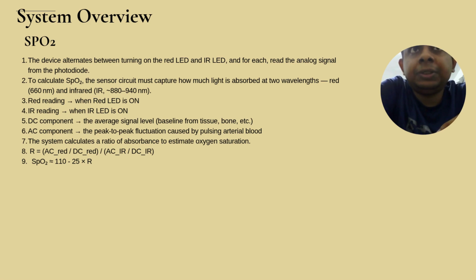So now for the SpO2, the device alternates between turning on the red LED and the infrared LED for each reading of the analog signal of the photodiode. To calculate SpO2, the sensor must capture how much light is absorbed between two wavelengths: red, which is 660 nanometers, and infrared, which is 880 and 940 nanometers. Red read is when the red LED is on. IR read is when the IR LED is on.